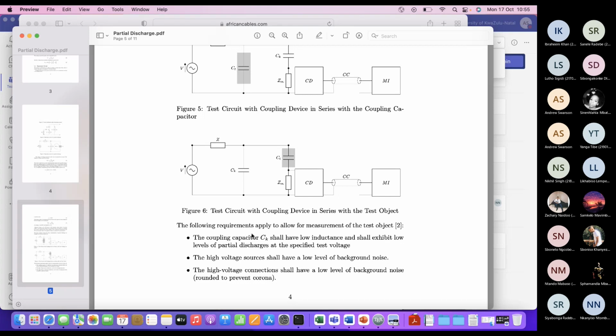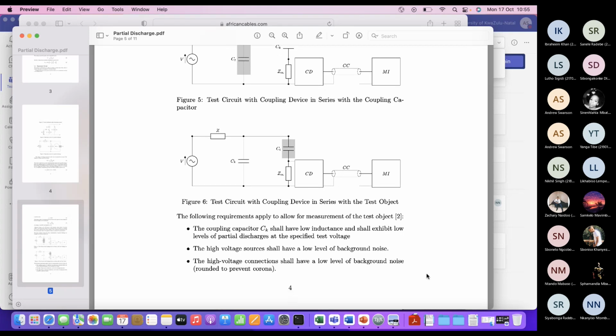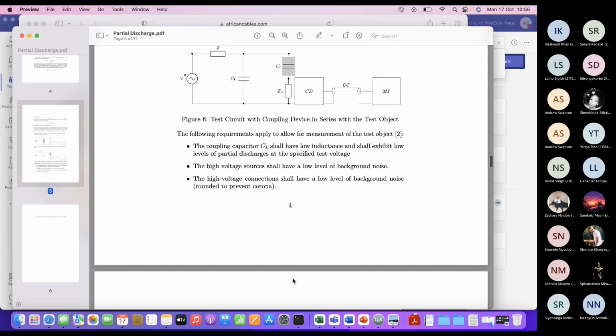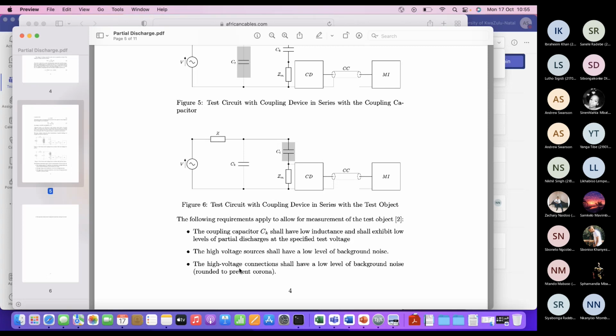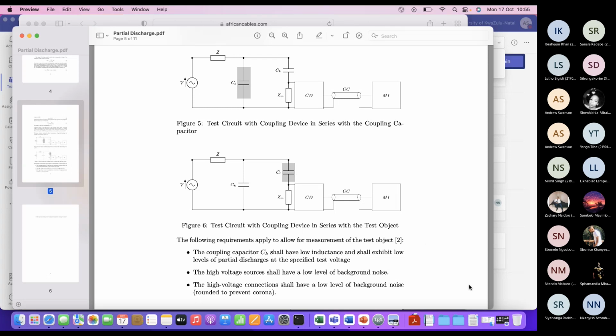There are a couple of important aspects to the setup. You can read through some of them yourself, but I want to point out that Z, that impedance there, has to be completely noise-free, and it needs to be of high enough value that it blocks any of those discharges. Those discharges you want to stay within your measurement circuit. You don't want them to flow through to the source. You want them to flow around your measurement circuit.